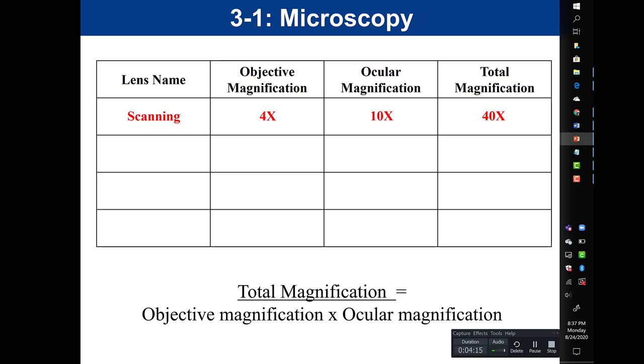The next biggest lens is the low power lens, with an objective magnification of 10x. That 10x objective combined with the 10x ocular gives a total magnification of 100x. The next lens is the high dry lens — high power but dry because it does not use immersion oil. The high dry lens must be kept dry; it cannot get oil in it. Its objective magnification is 40x, and with the 10x ocular the total magnification is 400x.